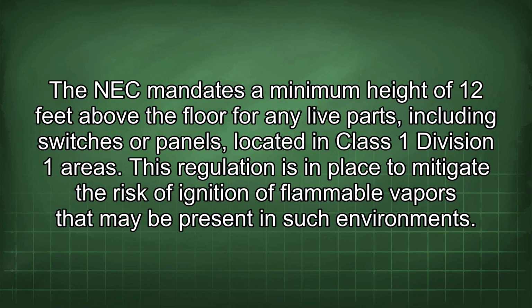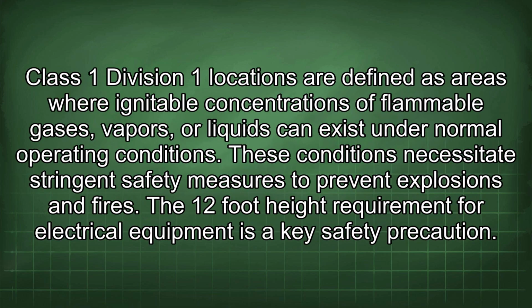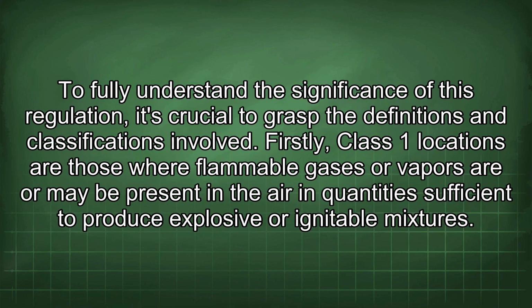This regulation is in place to mitigate the risk of ignition of flammable vapors that may be present in such environments. Class 1 Division 1 locations are defined as areas where ignitable concentrations of flammable gases, vapors, or liquids can exist under normal operating conditions. These conditions necessitate stringent safety measures to prevent explosions and fires. The 12-foot height requirement for electrical equipment is a key safety precaution. To fully understand the significance of this regulation, it's crucial to grasp the definitions and classifications involved.